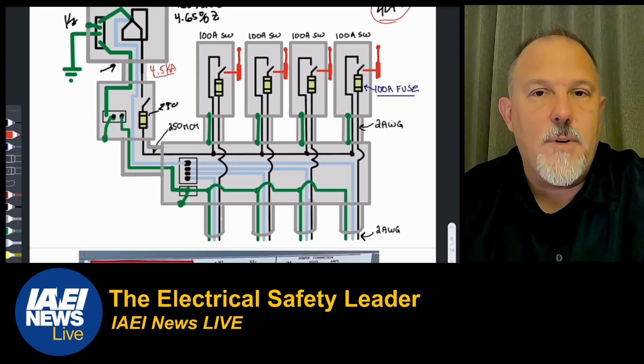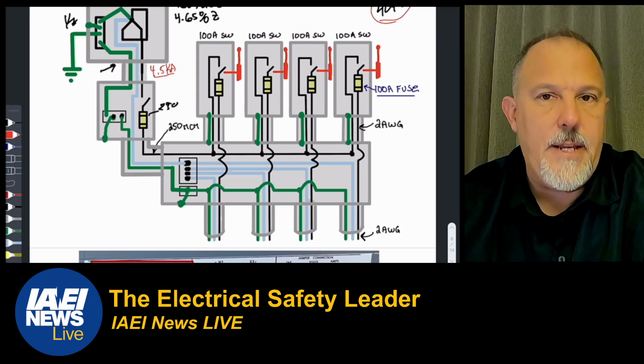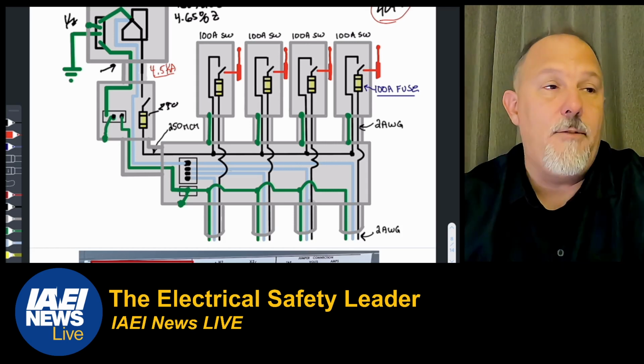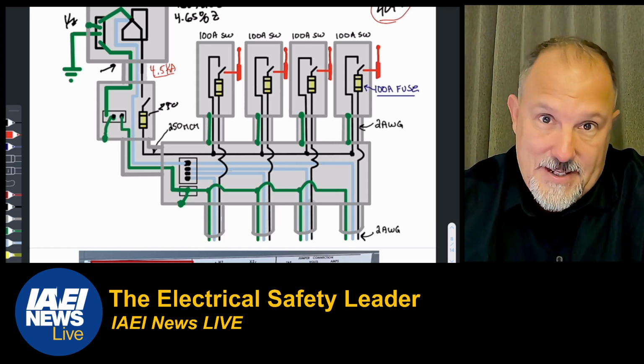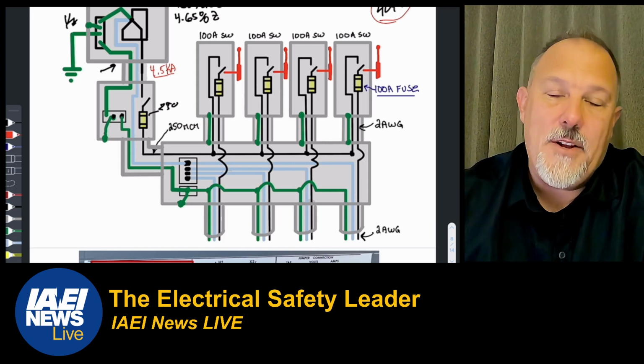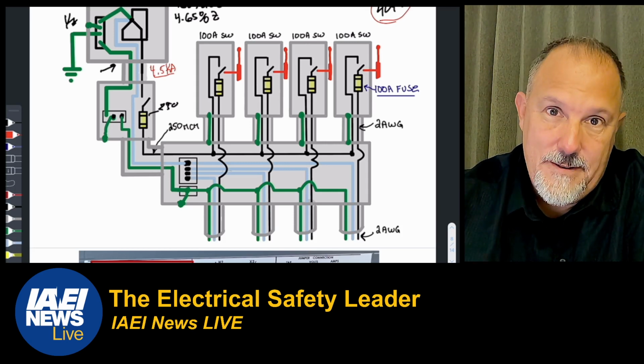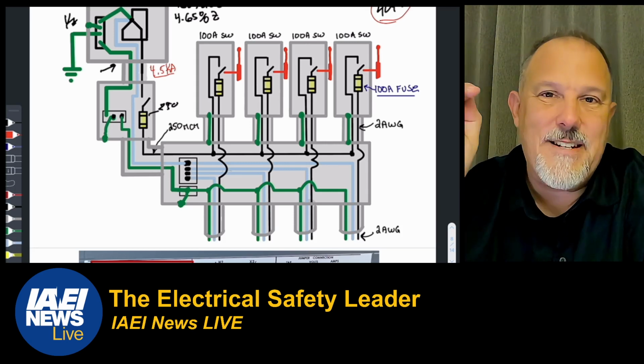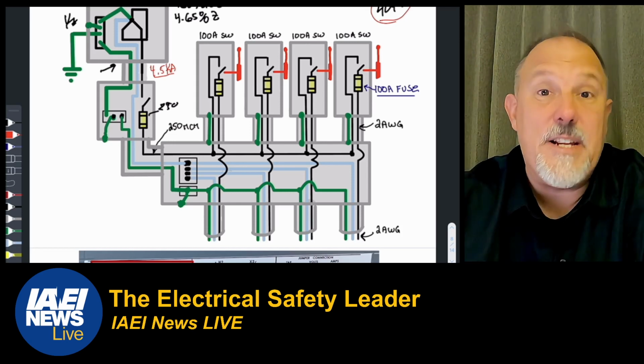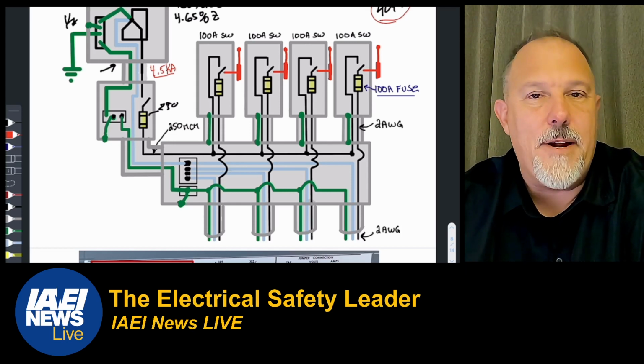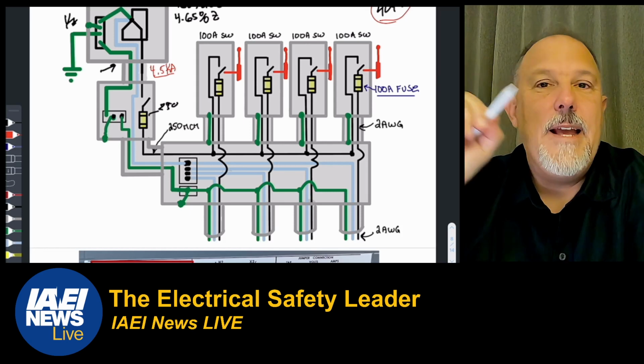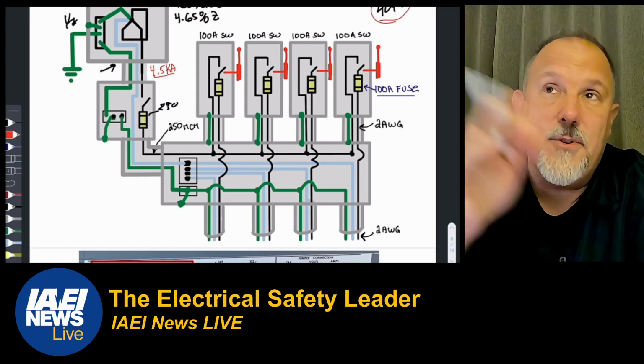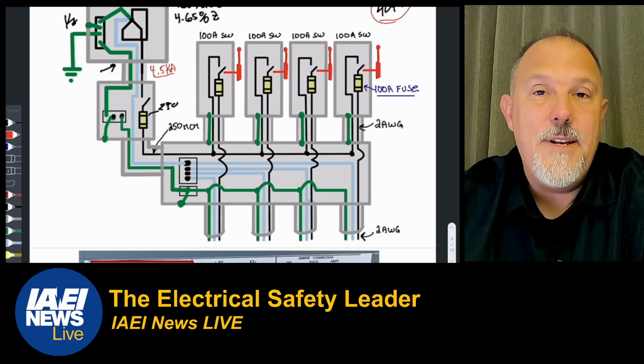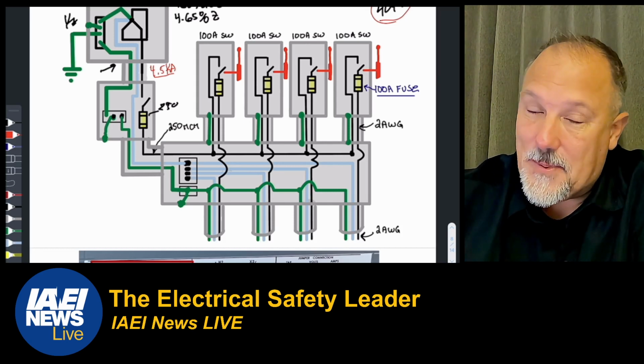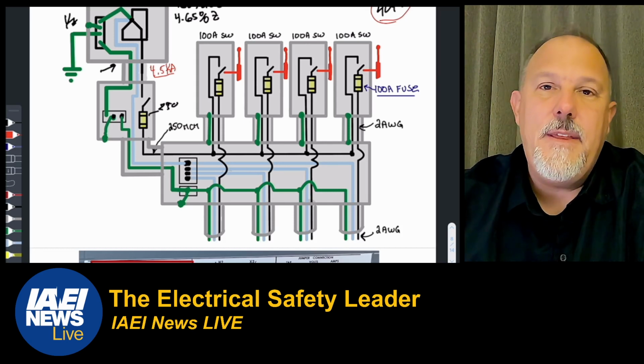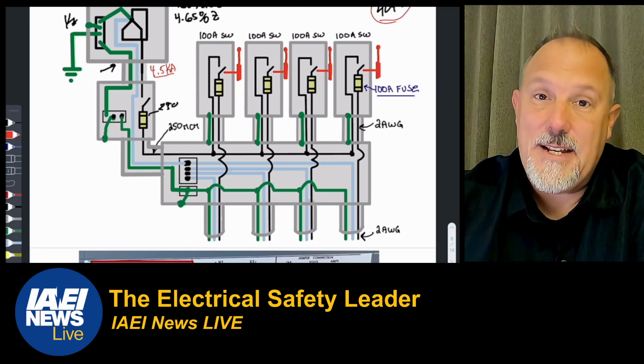And what was happening was that light switch would be there, and eventually somebody would say, hey, I want to put in an occupancy sensor. And when they put an occupancy sensor in, there's no grounded conductor, and the occupancy sensor needs to be powered. And how do you power it? You power it between hot and neutral. But there's no neutral down in that light switch. So what did they do? And even listed them this way, they connected the equipment grounding conductor to the light switch.